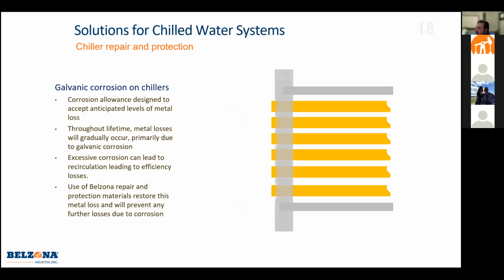So this is just a little animation showing your allowed corrosion. Now it's getting a little too far past the allowance. That's when, especially with roller expanded tubes, they start to leak between the tubes and tube sheets, giving you efficiency loss and can also be a little dangerous. So we come in, blast these, fill them back in flush with a paste, and then put a good 2-coat system of our ceramic epoxy.